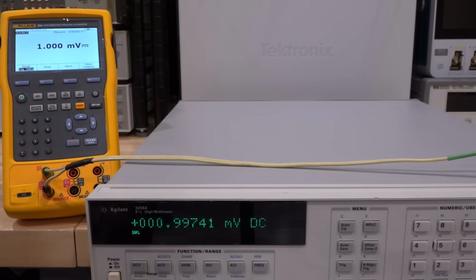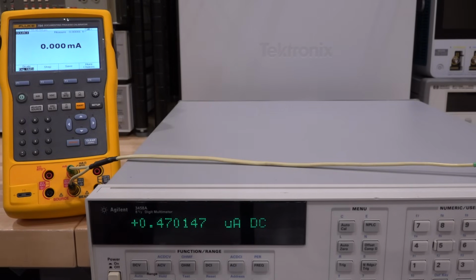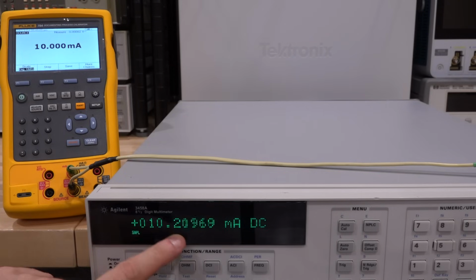We can also test the current, which hopefully should be based on roughly the same circuitry, and see if that works. So let's try 1 milliamp over here now. Yeah, that's quite a bit off. That is a little bit concerning. Let's try 10 milliamp. And yeah, oh yeah, that's way off. So there's something going on there. Perhaps there's something more than just the ohms measurements, or there's some overlap in the circuitry that's at fault, but this is way out of range.